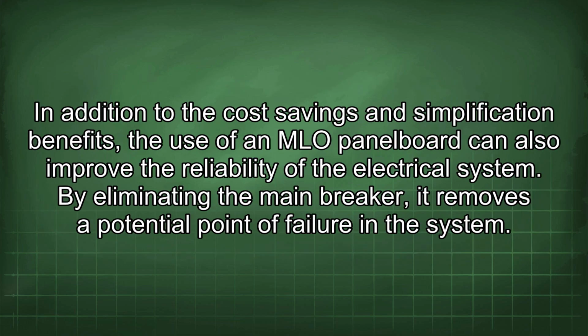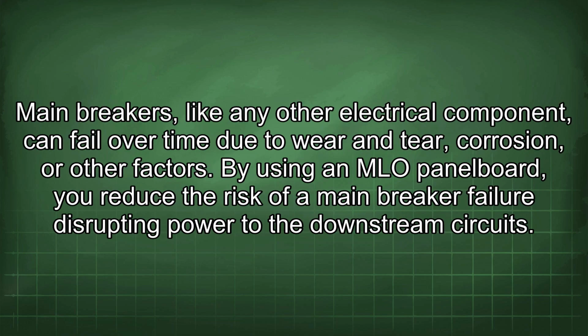In addition to the cost savings and simplification benefits, the use of an MLO panel board can also improve the reliability of the electrical system. By eliminating the main breaker, it removes a potential point of failure in the system. Main breakers, like any other electrical component, can fail over time due to wear and tear, corrosion, or other factors. By using an MLO panel board, you reduce the risk of a main breaker failure disrupting power to the downstream circuits.